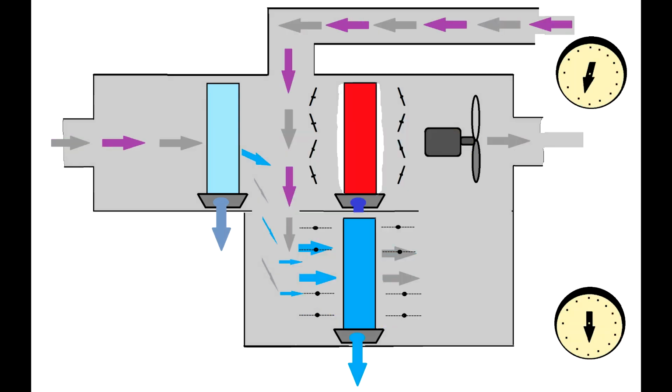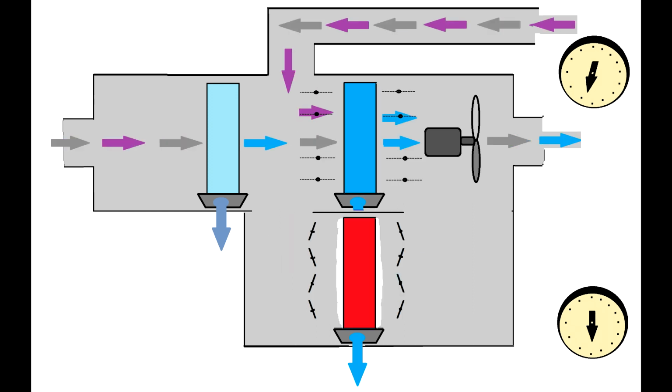Now coming back to my story, you will see here better that this air handling unit is using two heat exchangers. One is on duty and one is on defrost. The one which is on defrost has the dampers closed. You do not want to circulate the air through the very hot heat exchanger which is on defrost. And then on the right hand side you have two gauges. The gauges are measuring the pressure drop across the heat exchanger. So it's kind of monitoring the ice contamination.